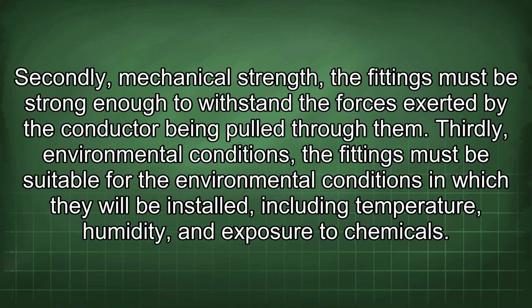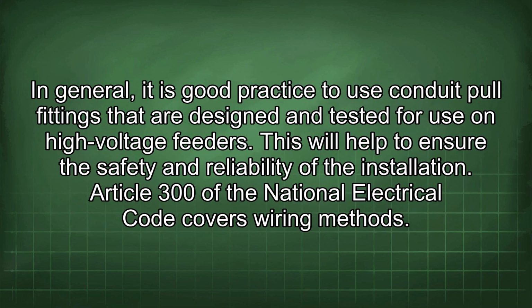Secondly, mechanical strength. The fittings must be strong enough to withstand the forces exerted by the conductor being pulled through them. Thirdly, environmental conditions. The fittings must be suitable for the environmental conditions in which they will be installed, including temperature, humidity, and exposure to chemicals. In general, it is good practice to use conduit pull fittings that are designed and tested for use on high voltage feeders. This will help to ensure the safety and reliability of the installation.